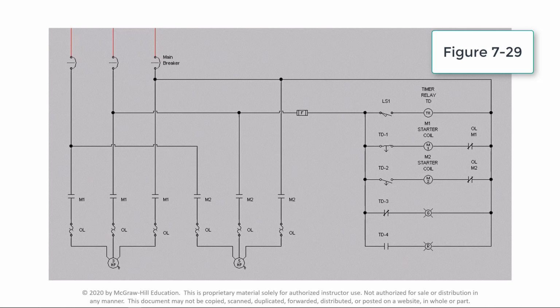When power is first applied, with limit switch LS1 open, motor starter coil M1 is energized and the green pilot light is on. At the same time, motor starter coil M2 is de-energized and the red pilot light is off. When limit switch LS1 closes, off-delay timer coil TD energizes. As a result, time contact TD1 opens to de-energize motor starter coil M1.